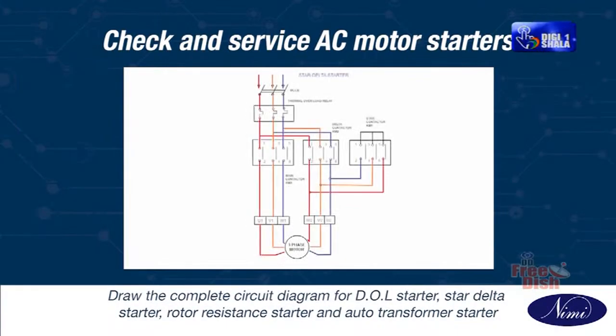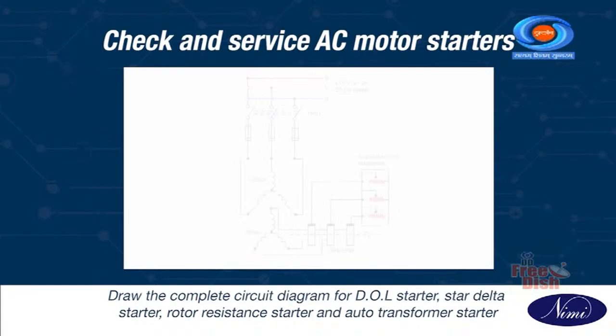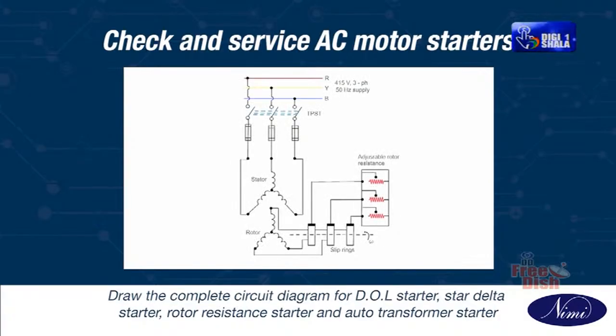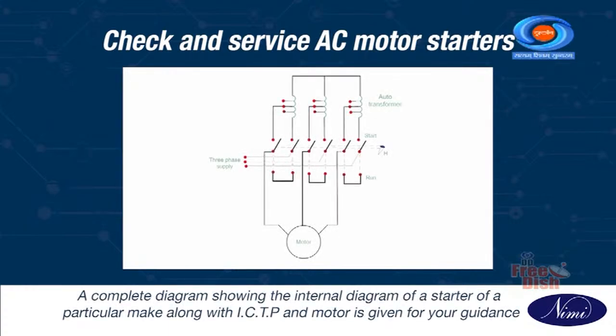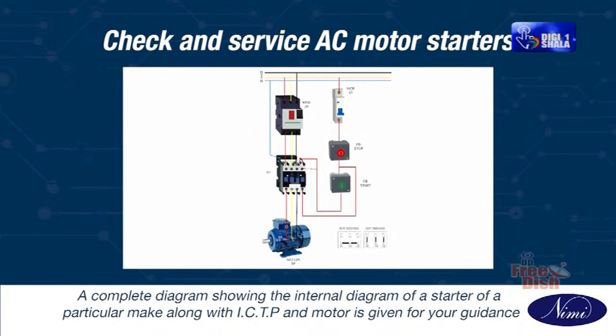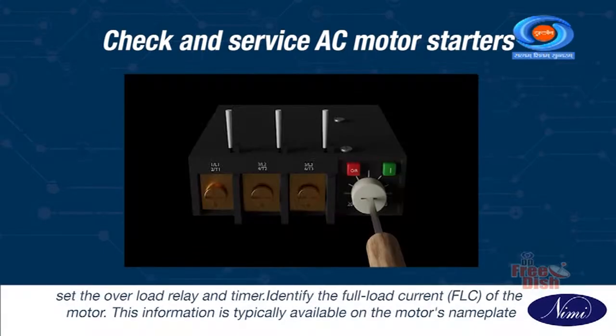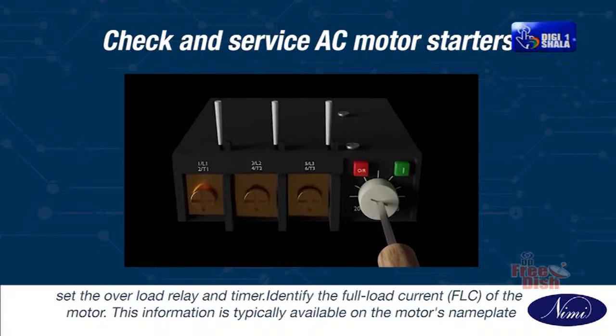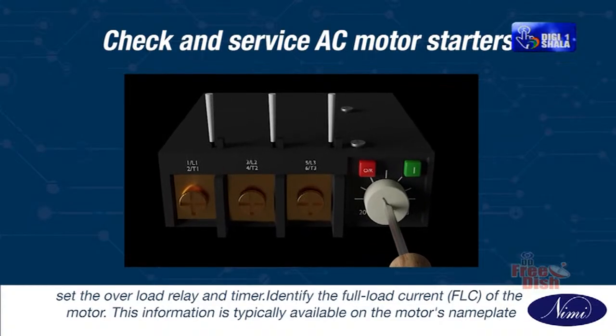Draw the complete circuit diagram for DOL starter, star delta starter, rotor resistance starter and auto transformer starter. A complete diagram showing the internal diagram of a starter of a particular make along with ICTP and motor is given for your guidance. Set the overload relay and timer. Identify the full load current FLC of the motor.